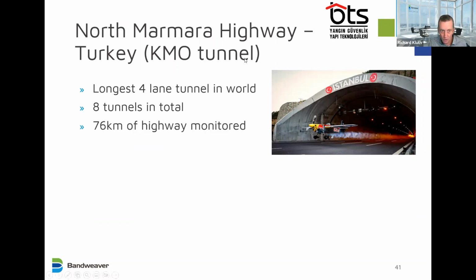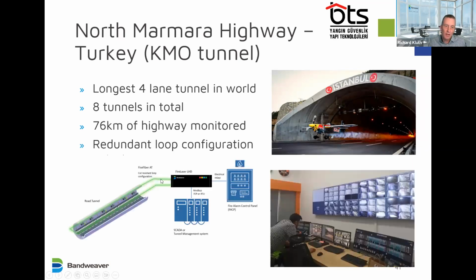So BTS installed 76 kilometers of fiber for fire laser in these tunnels. Again, redundant loop configuration, so that if there's any cut to any of the cables, you have complete cable redundancy. Again, connected to the SCADA system. You can see the control room here, the SCADA system, and connected to the fire control panels via the relays.